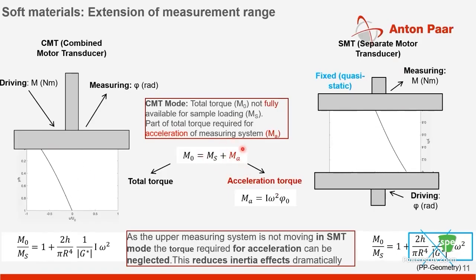And typically the acceleration torque is the torque which is needed to accelerate the measuring system. And typically it has an omega square scaling. And that's why if you do some simple quick math, and if you take a ratio of the total torque to the sample torque, in the CMT mode, it scales as omega square. And this is what you see at the really, really high frequency. You see that spurious increase where your data is now affected by instrument inertia.